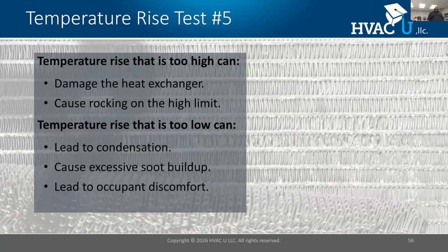When the temperature rise is too high, it can cause rocking on the temperature limit. Rocking on a temperature limit is when the limit switch that we discussed earlier opens up and shuts the equipment down. The limit is auto reset, so when it cools off, it closes back. But my airflow problem is still there, so it opens, then it cools off and closes back. When you have a piece of equipment that stops all of a sudden and then comes back on all by itself, it could likely be that you're rocking on a temperature limit.